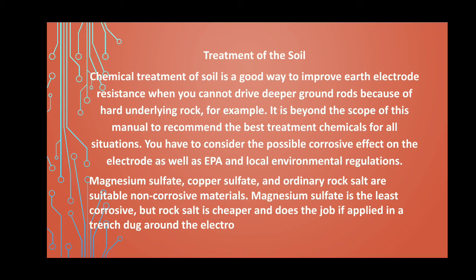Magnesium sulfate is the least corrosive, but rock salt is cheaper and does the job if applied in a trench dug around the electrode. So these are also essential things to improve the earth resistance. That is the chemical treatment.